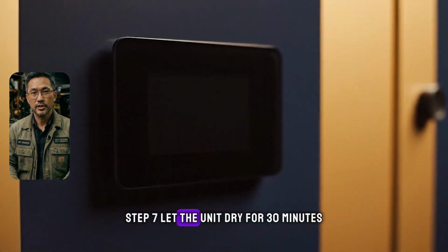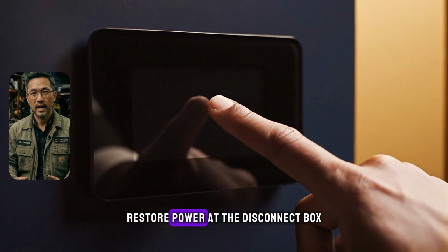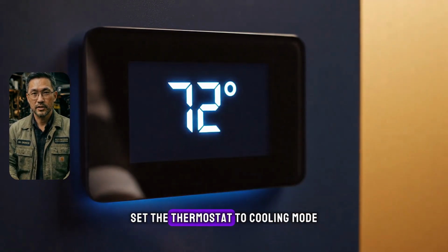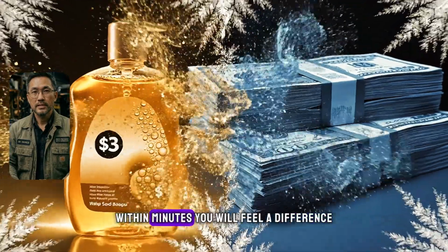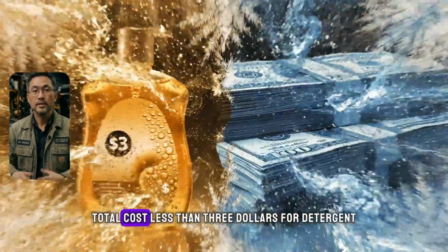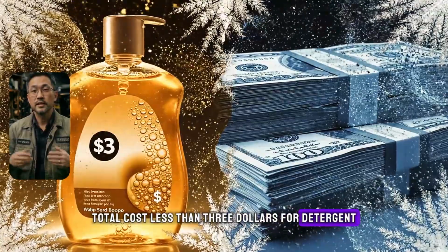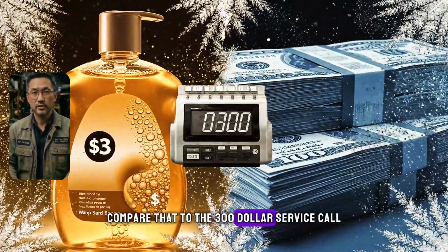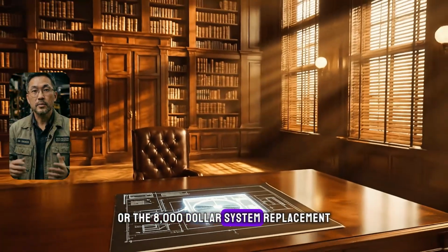Step 7. Let the unit dry for 30 minutes. Restore power at the disconnect box. Set the thermostat to cooling mode. Within minutes, you will feel a difference. Total cost, less than $3 for detergent. Compare that to the $300 service call or the $8,000 system replacement.